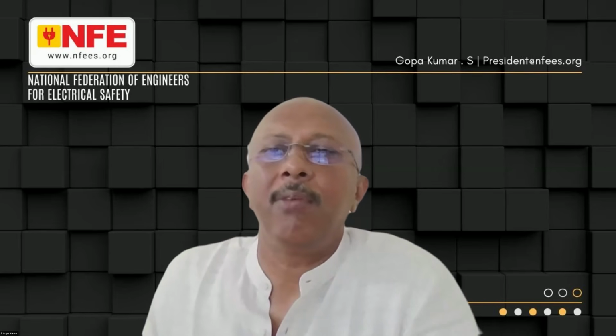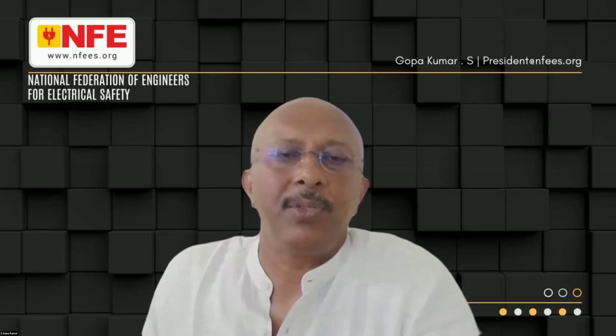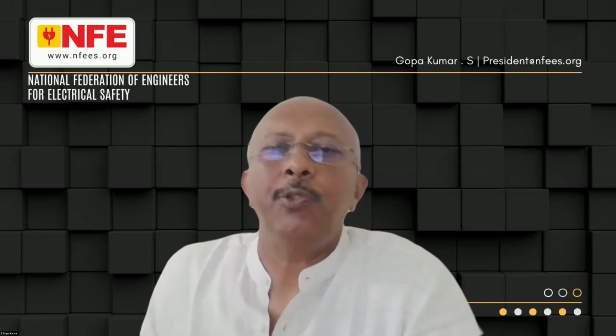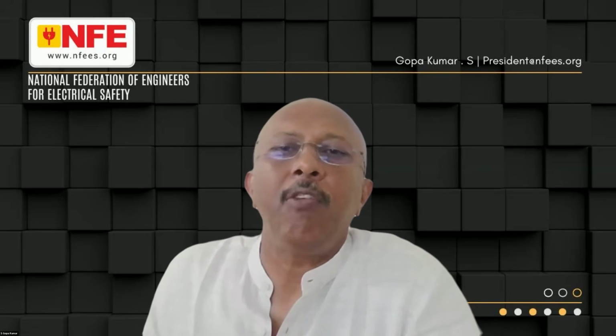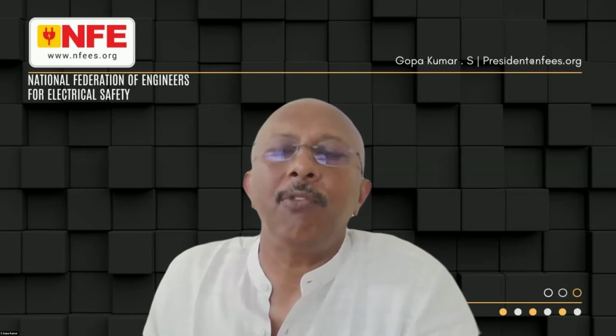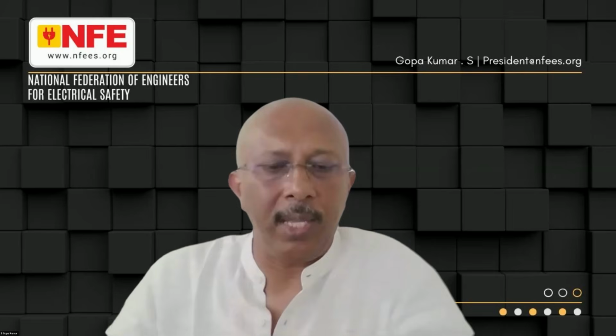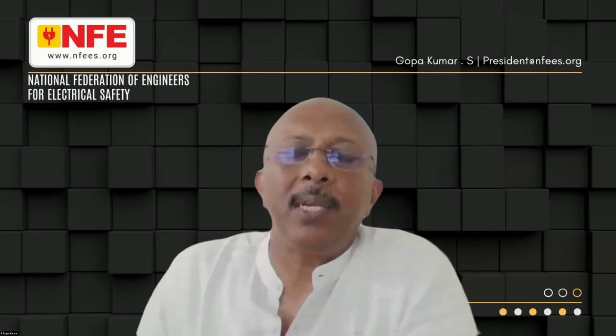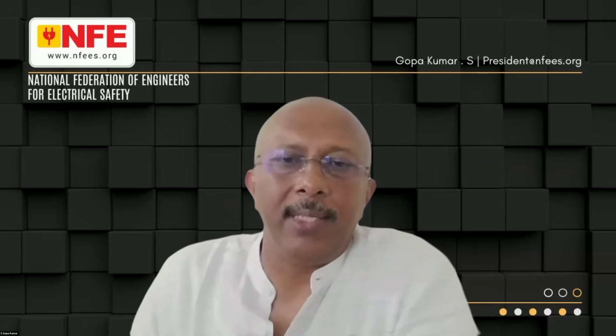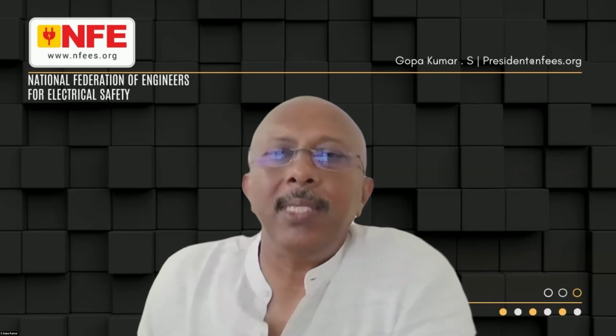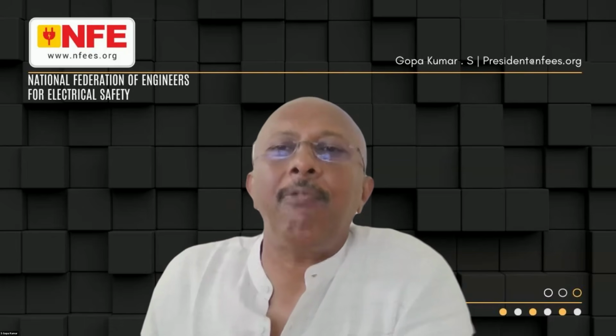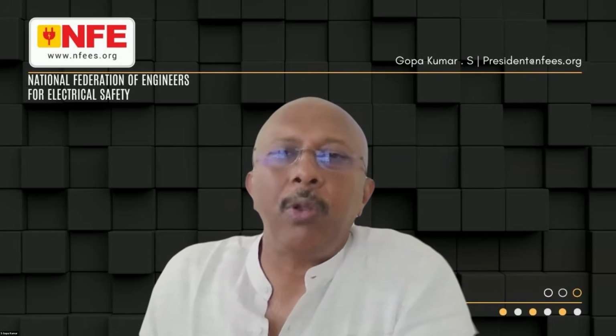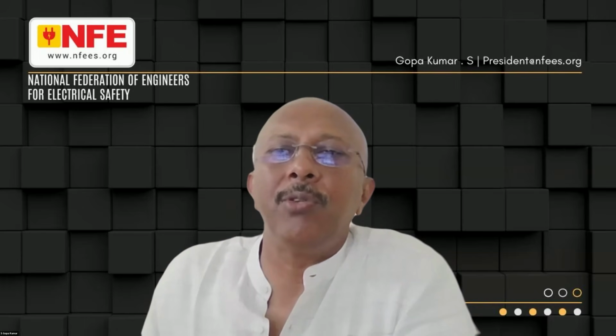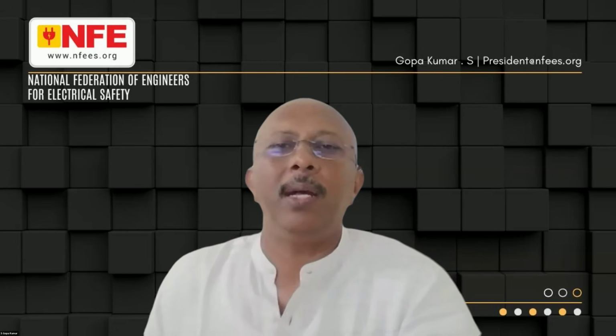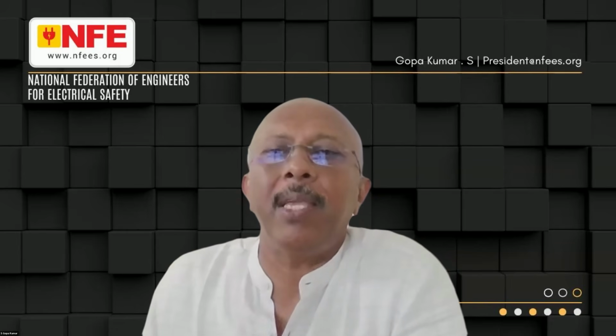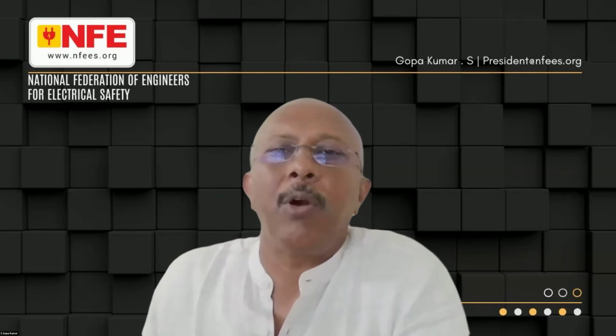Now, the next question is from Ms. Hemalata. If the area is space constrained or rocky after completion of the building, how do we design the earthing system for all equipment, transformers? Please note that the best way is to think about the electrical installation and the earthing system at the beginning of your electrical installation, not after making the building. You can make use of the structural steel which is used in the building, and you can make a very good earthing and equipotential bonding system by making use of the steel with a little bit of additional modifications.